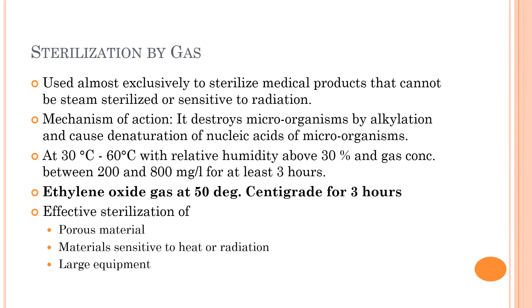For example, if you have a dental clinic, you can own a hot air oven or an autoclave, which is easy to maintain. It doesn't require any major apparatus. You can buy it commercially and set it up and use it in your clinic. But to have ethylene oxide, you need to have industrial regulations and permissions, because it's a flammable gas. You cannot keep it in a domestic area. It is a risk for all the people around that area. So usually ethylene oxide is available only in big institutions or industrial sterilization, in the manufacturing area, when they manufacture the plastic instruments or things like that. They will sterilize it in the industry and then send it across to the market. So that is the area where they use the ethylene oxide gas.